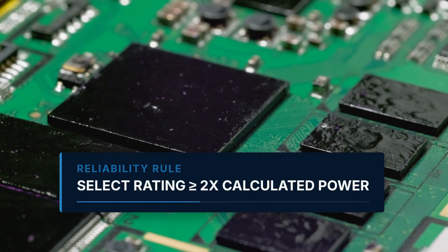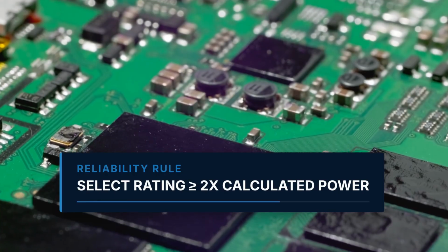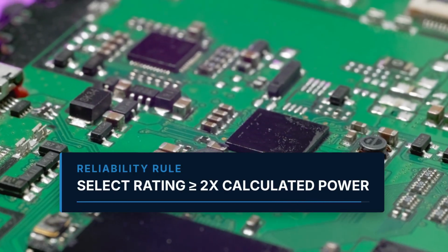Here's a critical insight. Always select resistors rated at least double your calculated power dissipation for reliability and thermal management.